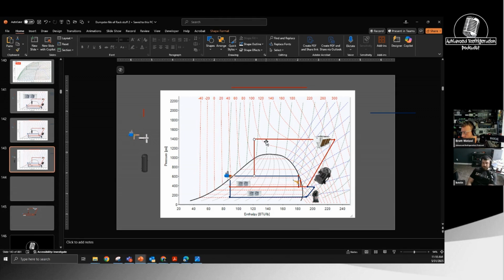Okay, so let's guesstimate this in pressure. You said you were running about 1400, yes? Yeah, about around 1400. And your drop leg temperature sensor was about 96? Yep. So even at that, this isn't totally exact, but there's your 10, 20, 30, 40, about 50, so you're about 45% vapor and about 55% liquid. That's what it's showing here.